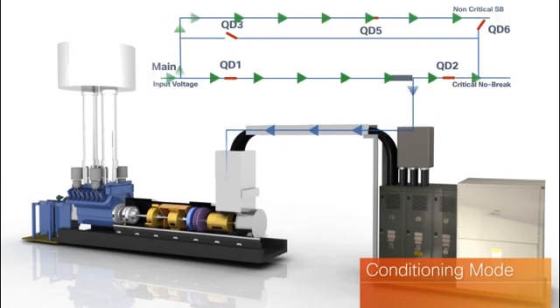In this mode, the rotary UPS system provides continuous power conditioning by regulating the output voltage, power factor correction, harmonic distortion filtering, and also protects against spikes, sags, and other anomalies.